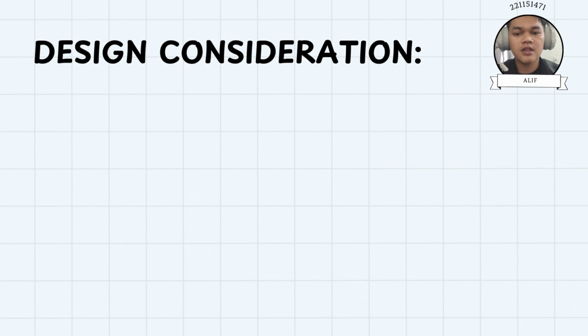Let's go to the design considerations, mechanical and morphological. In terms of mechanical considerations, the implant must have high fracture strength to withstand repeated cyclic loading. It must also have adequate stiffness to support body weight while maintaining an elastic modulus close to the bone to reduce stress shielding. Additionally, high wear resistance is required at the articulation surface to ensure a long service life.